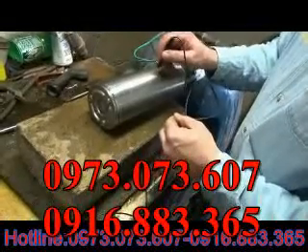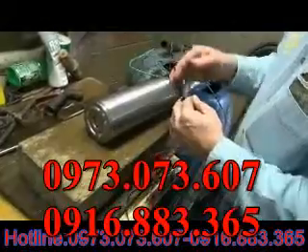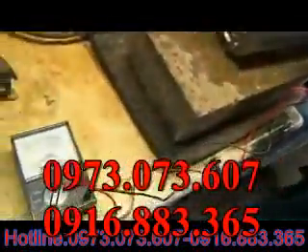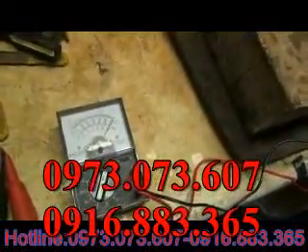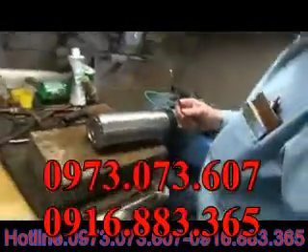If we're shorted out, you theoretically could get juiced. Now I can go between the two wires to check continuity right through the windings of the motor. And that should work? That should work. Oh yeah, that does. The needle goes all the way there. So if that were down, that would indicate a problem too then? Yes, it would.